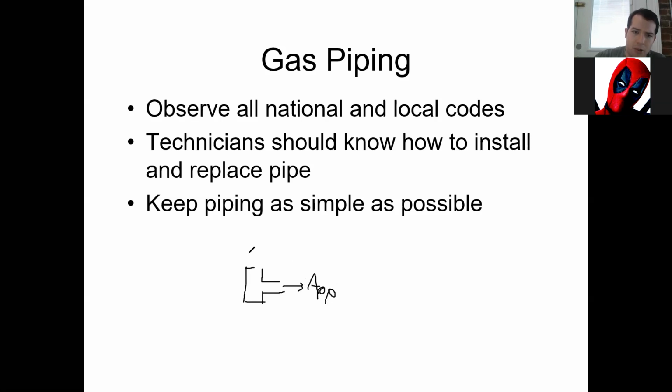And then you've got this line is your main, and then you'll have this little cap at the end. It'll be just a straight piece, just a cap on the end of it. If anything is in that gas line, whether it's rust, debris, anything that could have gotten in there over time, or any stuff that gets in the natural gas itself, we'll be able to collect at that bottom, and you can actually empty those caps and clear out the gas line, basically.